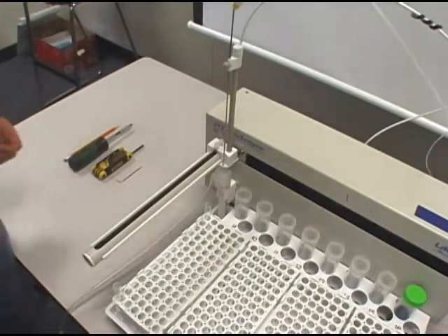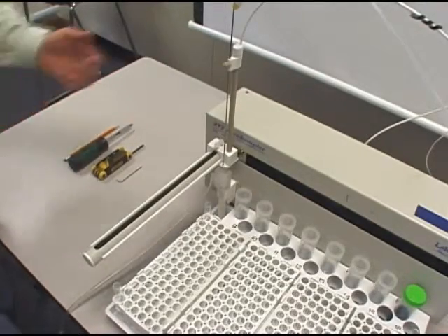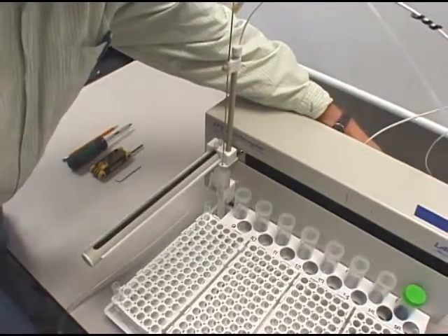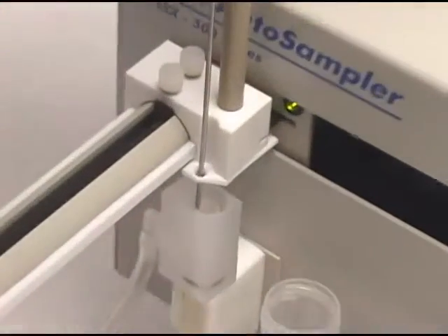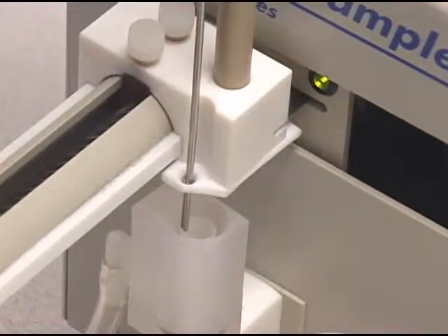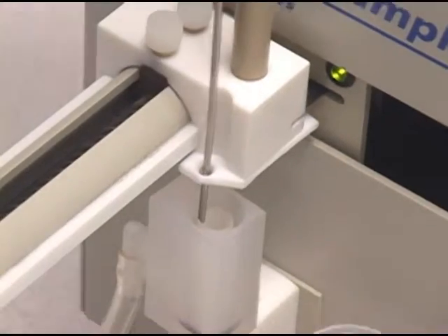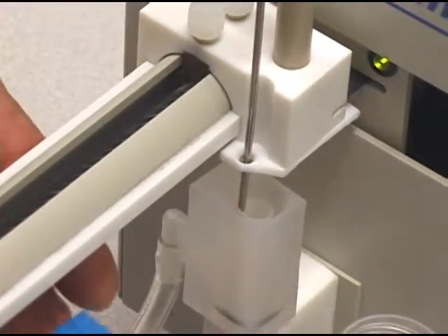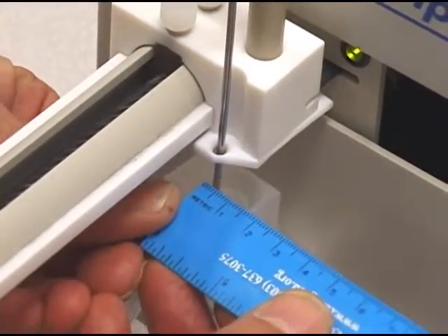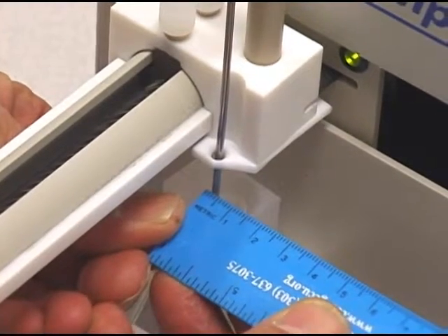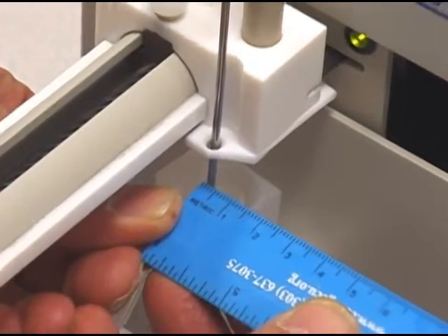We're now going to show how to adjust the wash bath so that it is centered, so that the probe is centered in the wash bath. You can see here that the probe is a little bit to the left in going into the center of the wash bath. The first thing we want to do is to measure how far off that probe is and what it would take to move it to get it into the center of the wash bath.